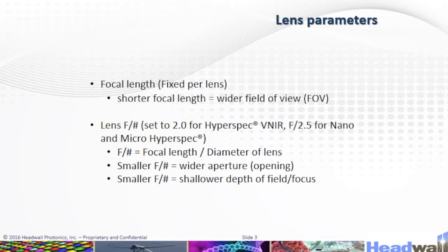Here we have the lens parameters. Focal length is fixed per lens. A shorter focal length gives a wider field of view. The F-number will be set to 2.0 for Hyperspec VNIR and 2.5 for Nano and Micro Hyperspec. F-number equals focal length divided by the diameter of the lens.